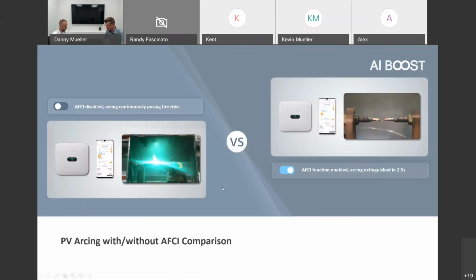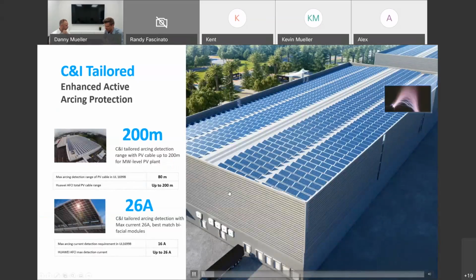Huawei is certifying their AFCI detection circuits as any other manufacturer under the UL1699B. And Danny is displaying here a video from a typical ARC scenario. With a DC arc situation, opposite to an AC arc scenario, a DC arc can be maintained for a prolonged time and is not extinguishing itself based on the pure structure of a DC incident. And that prolonged arc has a lot of heat and a lot of energy in it and can lead to fire incidents and burning some shingles or whatever you have on your roof.